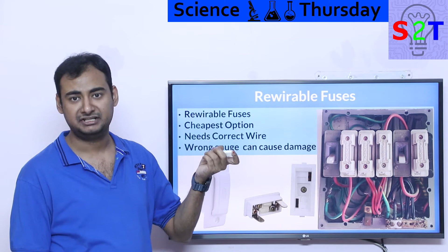Let's start with something very simple that all of you must have used: the rewirable fuse, basically something like this. If you're watching this in India, any switchboard near you will likely have something like this. These are awesome because they are very cheap, and once they blow, you can replace it with a good conductor, super easy to use. But the problem is that a person can directly replace the conductor inside, basically spool another wire there. You need the correct wire, and that's far more problematic than you'd think, because you'll think, hey, this is designed for 20 amps.